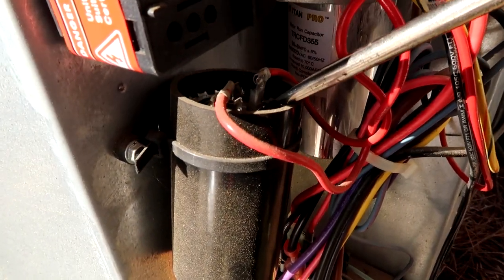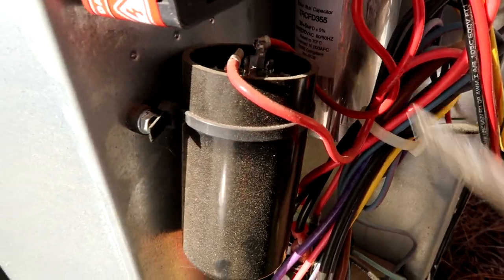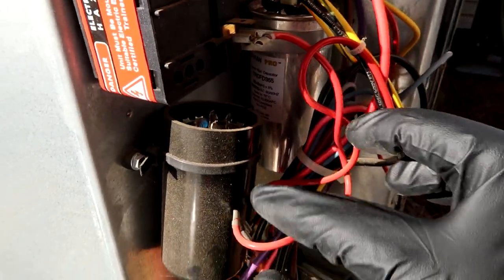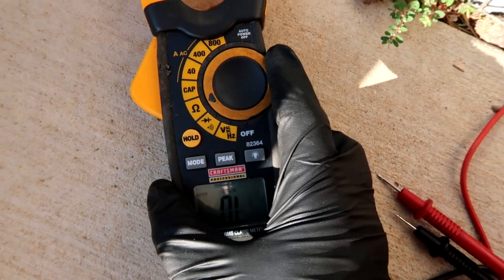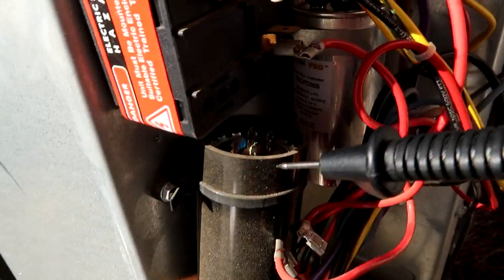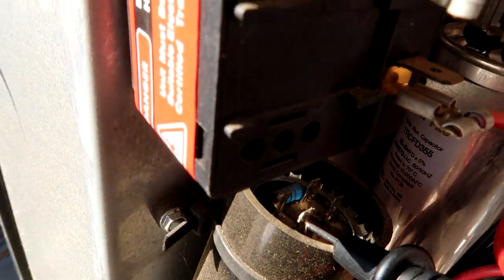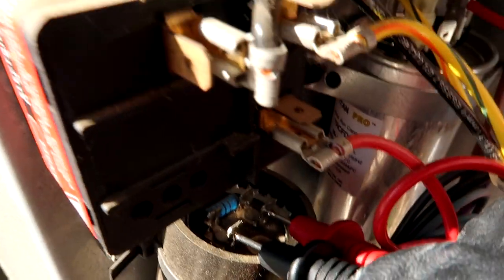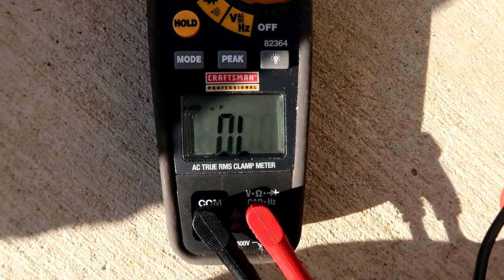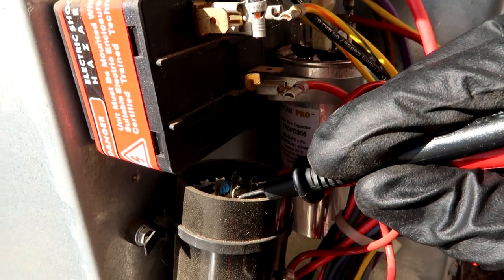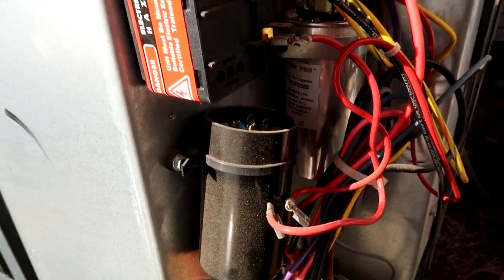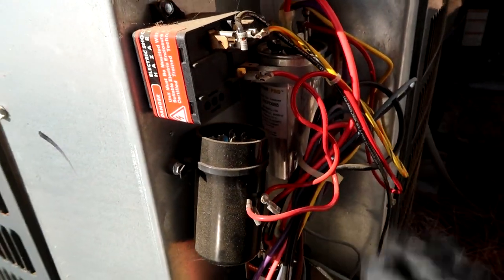Just take off the two wires. Put our meter on cap. If you've got a Fieldpiece or some other meter it would be MFD, but my Craftsman says cap. A lot of guys ask how old that thing is - I bought it like in 2007 or 8. That meter has been a good one. Leads on both of the terminals. This thing should be between 88 and 108, and as you can see we're getting zero. So this hard start is bad and that's why it's tripping the breaker. Seeing it many times out here. I'm just going to replace this whole deal, both that and that, just go all new.